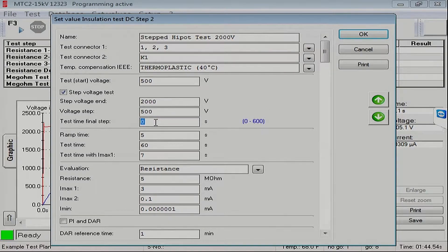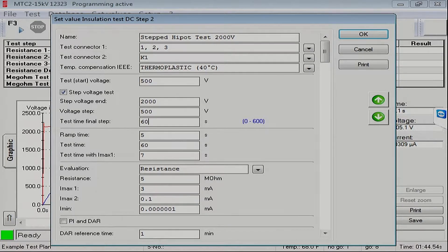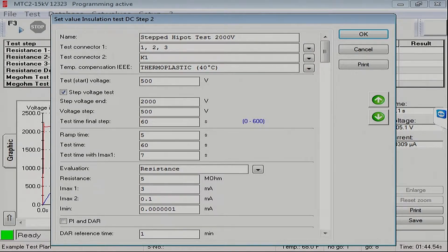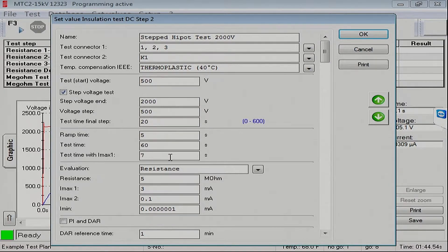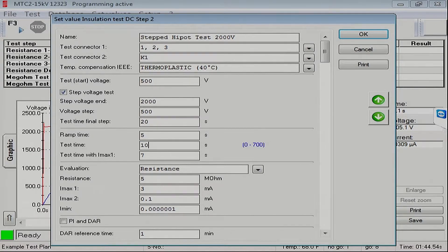And for the final test time, normally we would put 60 seconds so that we get a fully compliant IEEE 95 Hypot test. Or we can just back this thing off to, say, 20 seconds for our little demonstration today. And I'm also going to change this test time to say 10 seconds, just so it doesn't take so long to run through this thing.